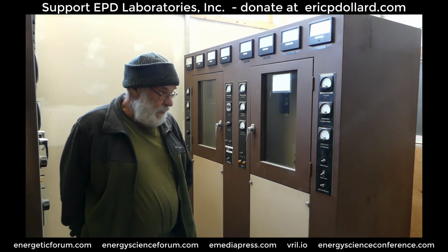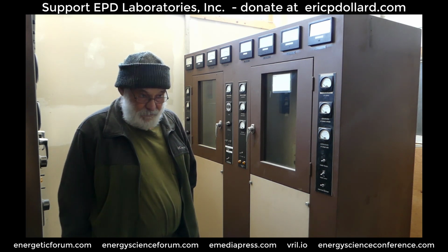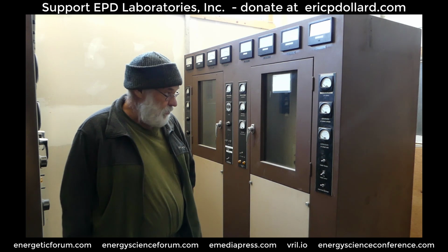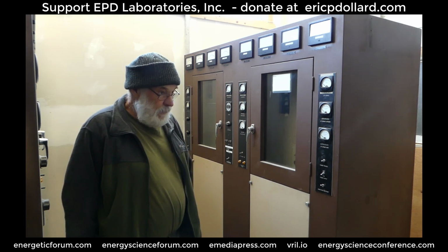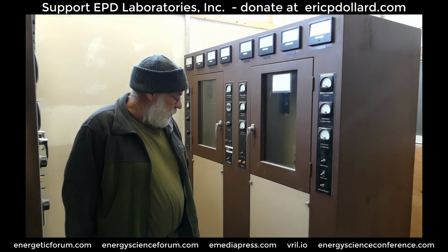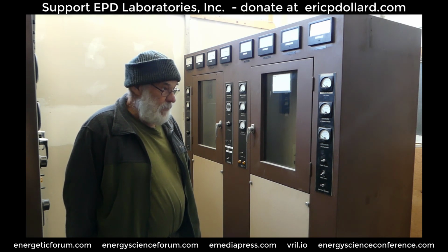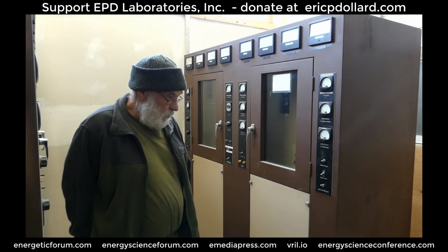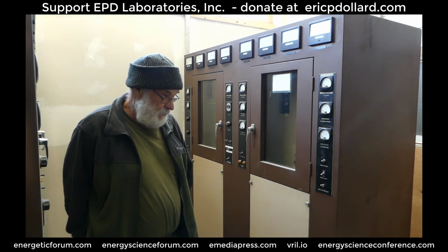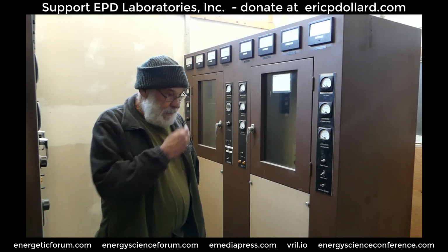14 gauge wire has 15 amp capability, so we'll get some high voltage 14 gauge wire and rebuild the rectifiers properly, putting them in an environment where there's no possible way there can be a cross connect between the high voltage and the low voltage side.